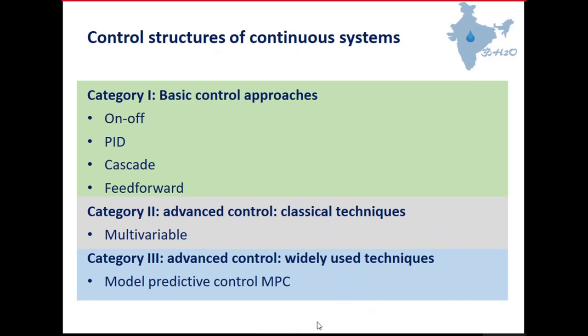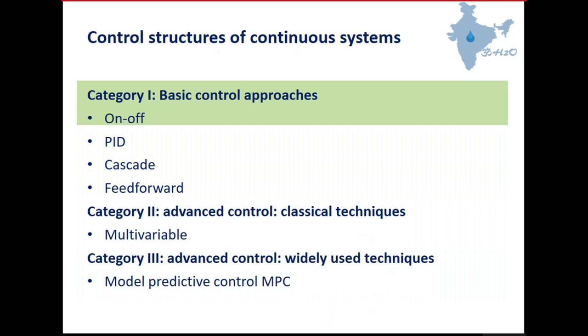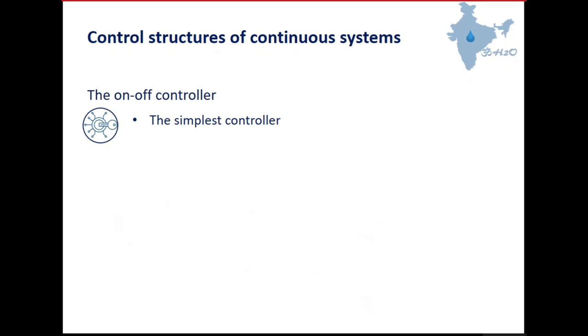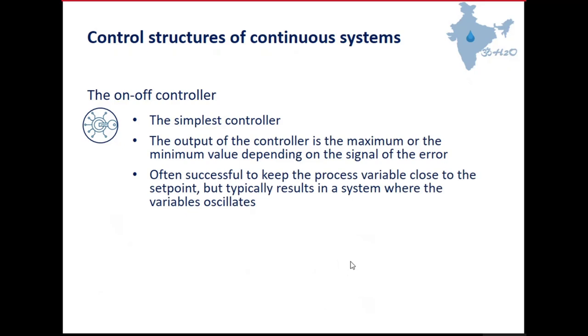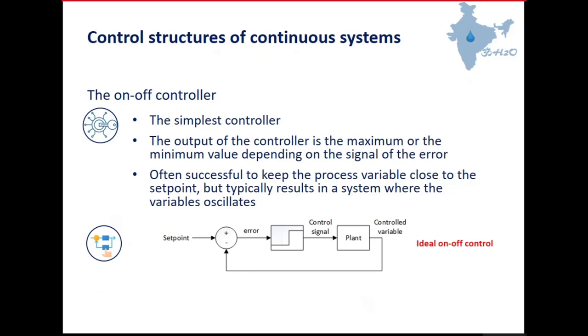Let's start with the on/off controller. The on/off controller is the simplest controller, and its output is the maximum or minimum value depending on the sign of the error. It is useful to keep the process variable close to the set point, but you can observe some oscillations in the result. In this scheme, you have your set point and controlled variable measurement, you calculate the error as the difference between the set point and the controlled variable, and depending on the sign of this error, your control signal is the maximum or minimum value applied to the plant.